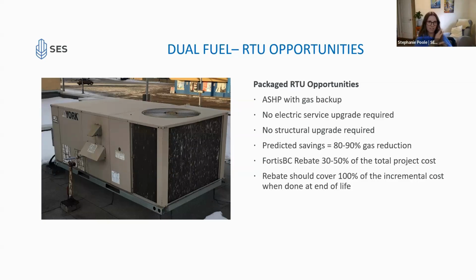Because you already have many of the same components in the new versus old system, chances are you don't need much structural upgrade. You might need a new pad. There may be some considerations if the newer unit is slightly bigger or a different shape, but it's typical that you wouldn't need a big structural upgrade. So the costs associated with the change are relatively minor. And here's the important thing: the predicted savings of a dual fuel rooftop unit can be 80 to 90%. I'd say maybe 70 to 90, depending on where you're operating it.